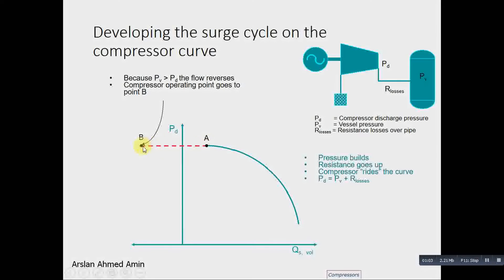Flow is reversed. Please note that the flow is reversed here, its direction is reversed. We know that for forward flow PD should be greater than PV. At the surge point, PV becomes greater than PD. That's why the reverse flow occurs.